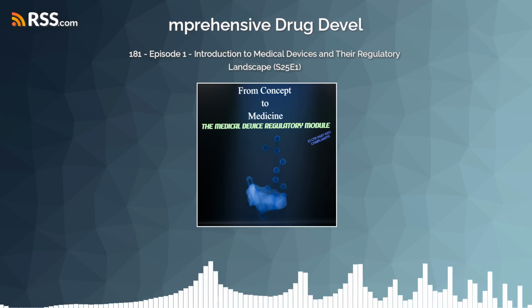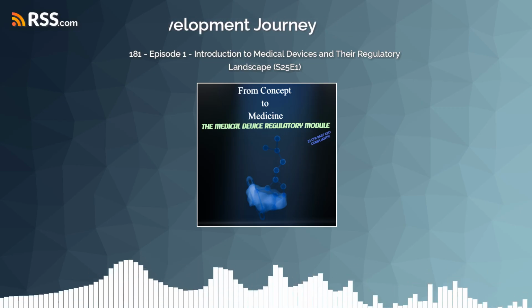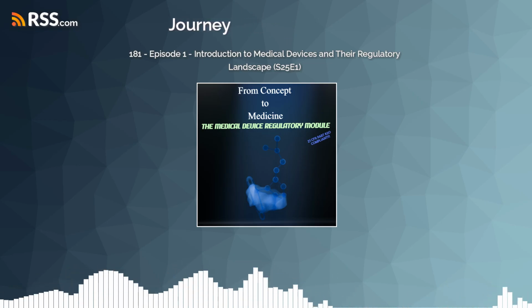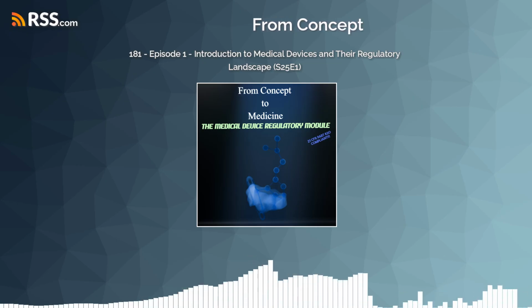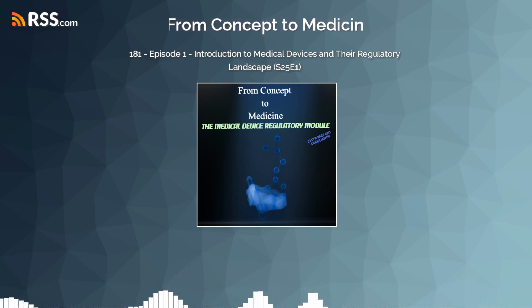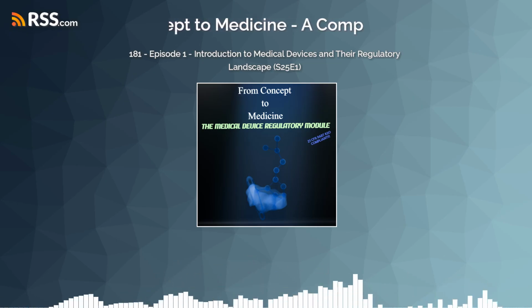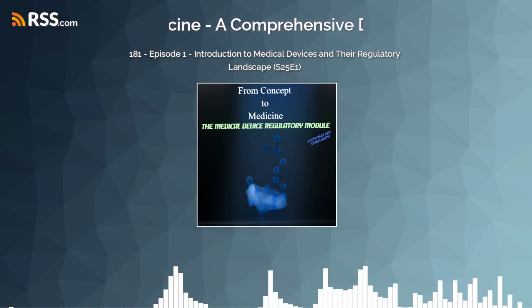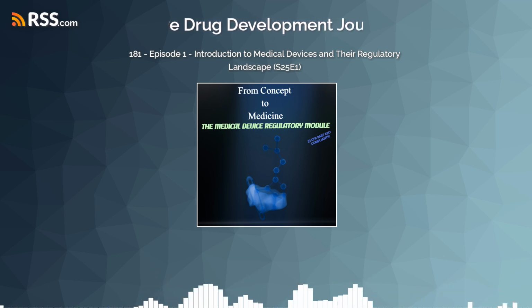Okay, three classes. And you're right, the regulatory control, the requirements, increase significantly as you go from Class 1 up to Class 3. So this sounds like a really foundational decision. It dictates the whole path forward for a company and its product. It truly is. This initial classification determines the entire regulatory pathway. It dictates what testing is required, whether you need clinical trials, which pre-market submission type you'll use, like a 510(k), a PMA, or maybe a De Novo request.